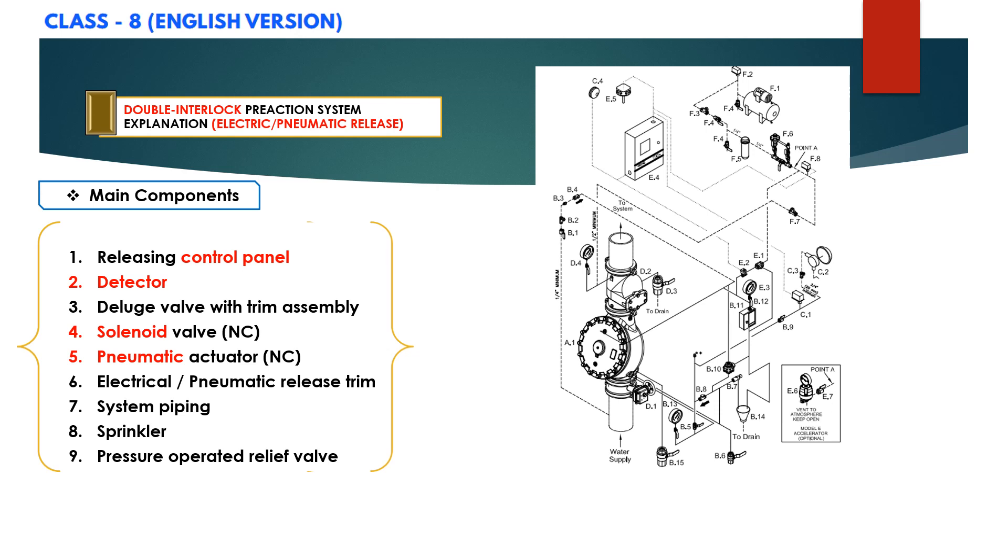Both the electric detection system must activate and supervisory pressure must be relieved from the sprinkler system before the preaction deluge valve will open to fill the sprinkler system with water.